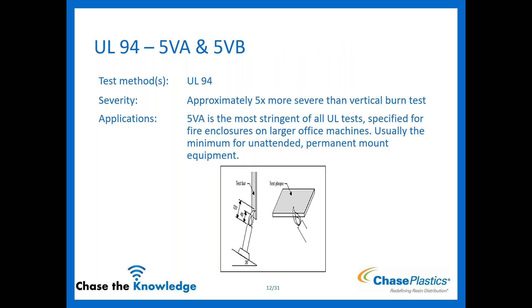Then your 5VA — these are approximately five times more stringent than your vertical burn test. It's a very stringent test: you apply the flame directly underneath a test plaque. The biggest difference between 5VA and 5VB is that 5VA does not allow burn-through, you cannot have the flame burn through the plaque, whereas 5VB does allow burn-through. An easy way to remember: B allows burn-through. It is typically specified for fire enclosures in larger office machines, and is the minimum for unattended permanent mount equipment.